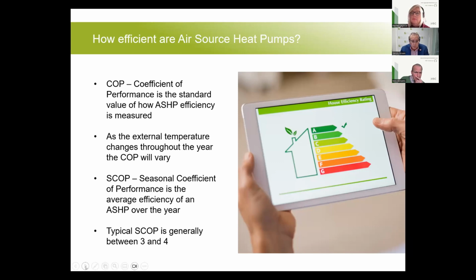Now, I've touched on temperatures. I can't do much about the outside temperature, but I can try to do more about the inside temperature. Fundamentally, the lower the inside temperature we can allow for heating, the less hard the heat pump needs to work to extract the latent heat, which means it's more efficient. In other words, the hotter the output temperature, the less efficient the heat pump is. So your design starts to come to a crossroads. If we're building a brand new house, we can put new radiators in and size them down to as low as 40 degrees. We'll do some examples on efficiencies there in a minute.